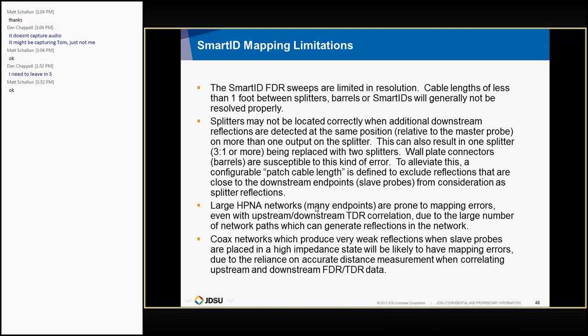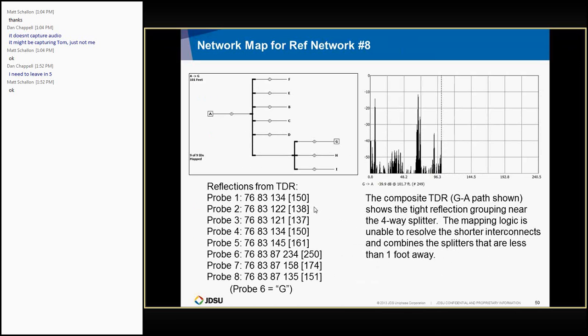Okay, large HPNA networks with a lot of endpoints are prone to mapping errors because there are too many reflections, and even with the correlation, you're going to run into too many other places where it's going to falsely correlate. The last point I make here is that you have to have an accurate distance between the master and slave for this correlation to work, because it depends on mirrored data correlating with the downstream data. So if you have a network where you just aren't getting a good reading on the high impedance termination at a slave probe, it can generate misleading mappings. So I just want to quickly show an example here.